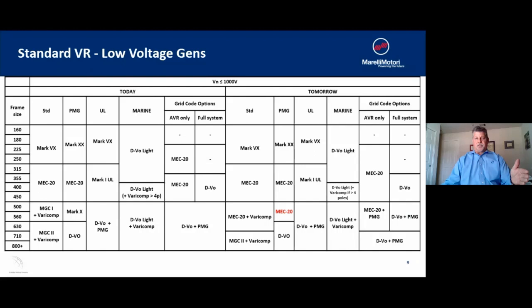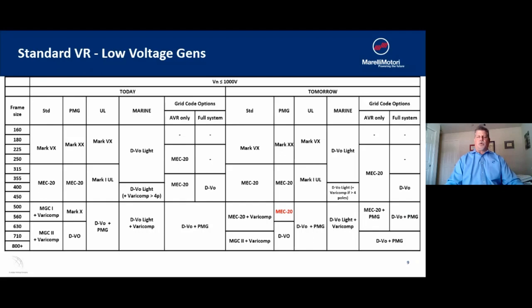The standard offerings: the 160 to 250 frame uses the Mark VX — that 250 frame is effectively 300 EKW. The next voltage regulator, for the 315 up to the 450 frame, is our MEC-20, which is very popular. We use the MGC1 with a Varicomp option on the 500 and 560 frames, and the MGC2 on the 630 frame and larger units. Depending on options chosen, we have different voltage regulators for PMG, UL, or Marine Society approved applications, and also what we typically recommend when clients are looking at purchasing a voltage regulator only, which would be interchangeable with other generator manufacturers.